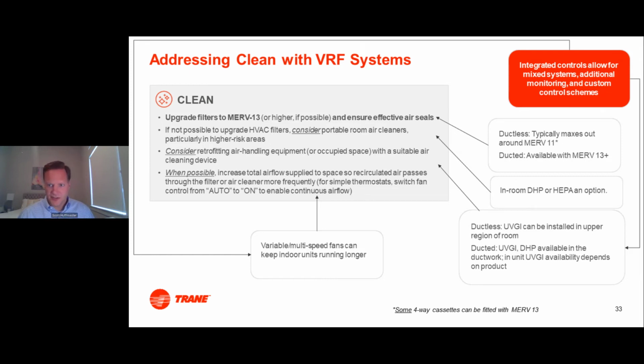Talking about filters. Okay, so you said MERV 13 filters. Well, how does that work for VRF? Well, a lot of times on ductless systems, it may not even be possible to achieve MERV 13. Typically, we'll see ductless systems that could max out around a MERV 11 level, and that's really about all that unit can do. Now, if we're focusing on this, you could look at ducted units because ducted units are available with MERV 13 or better.